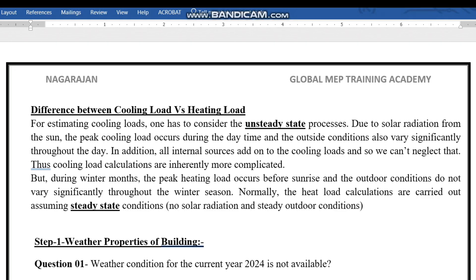First we need to understand why cooling load calculation is more difficult compared to heating load calculation. For estimating cooling loads, one has to consider the unsteady state process — due to solar radiation from the sun, the peak cooling load occurs during the daytime, and there are significant heat changes in outdoor conditions throughout the day. We also need to consider internal loads. For heating, the peak load occurs before sunrise and outdoor conditions don't vary significantly, so heating calculations assume steady state — no solar radiation and steady outdoor conditions.